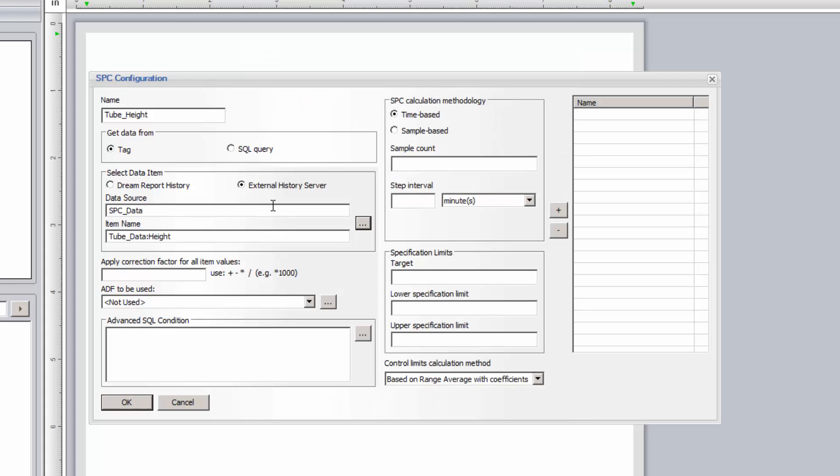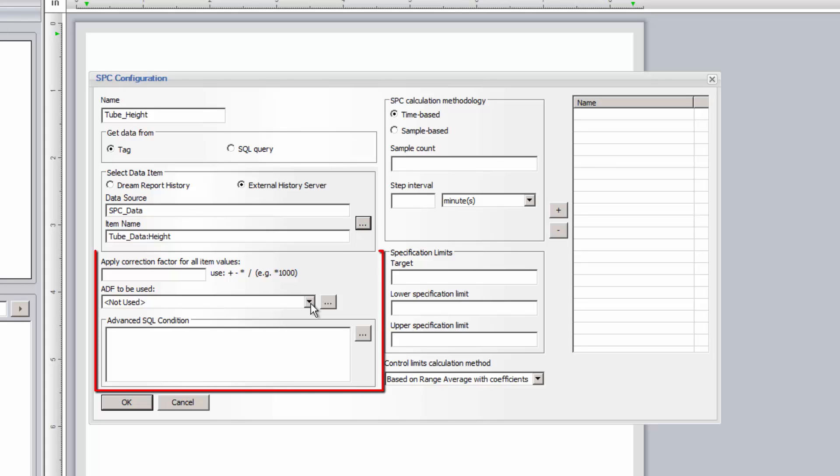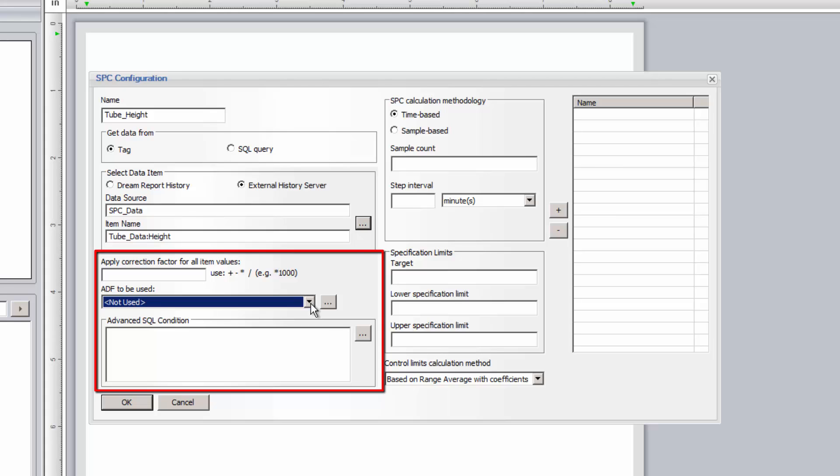SPC can either use the raw data as it was logged in the data source, or we can preprocess or filter the data, just as we could in any other DreamReport reporting object, before the data is used for the SPC reporting. We can apply a correction factor, apply an aggregated data filter, or filter the data based on some condition. For instance, only use the samples when product X was running.